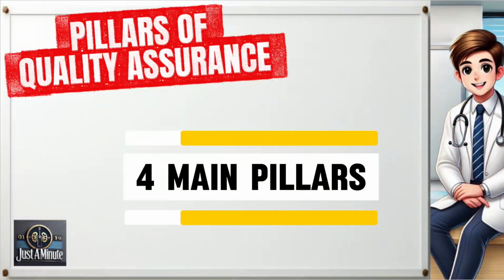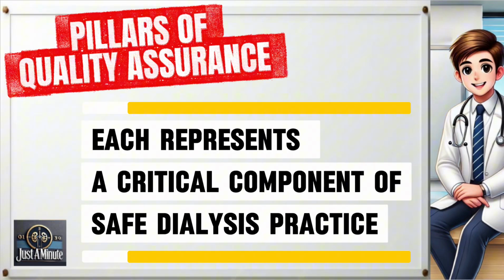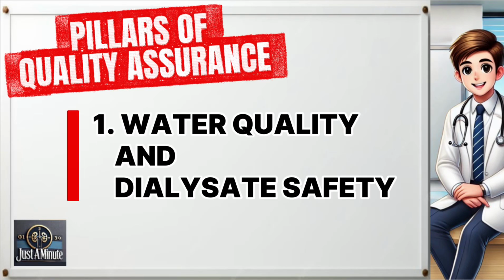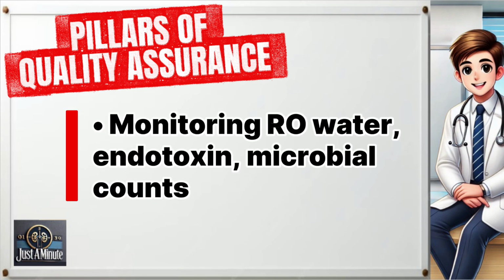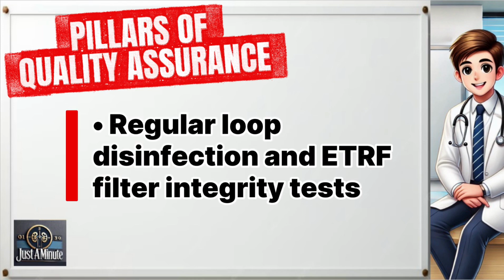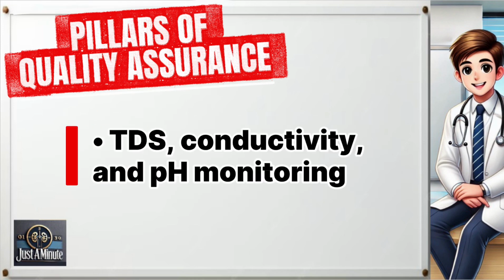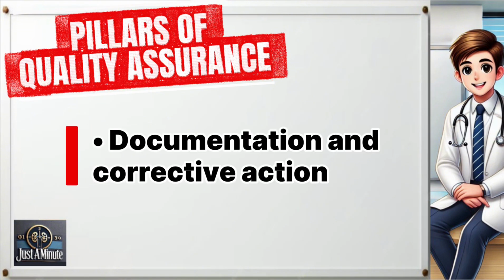Let's organize QA into 4 main pillars, each representing a critical component of safe dialysis practice. 1. Water quality and dialysate safety. Includes monitoring of RO water, endotoxin, and microbial counts, regular loop disinfection, and ETRF filter integrity tests, TDS, conductivity, and pH monitoring, documentation and corrective action when parameters exceed limits.